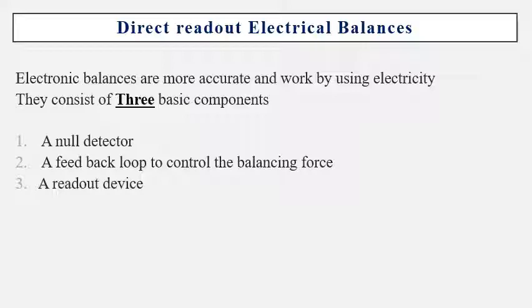Direct readout electrical balances are the most accurate and operate using electricity. They consist of three basic components: a null detector, a feedback loop to control the balancing force, and a relating readout device.